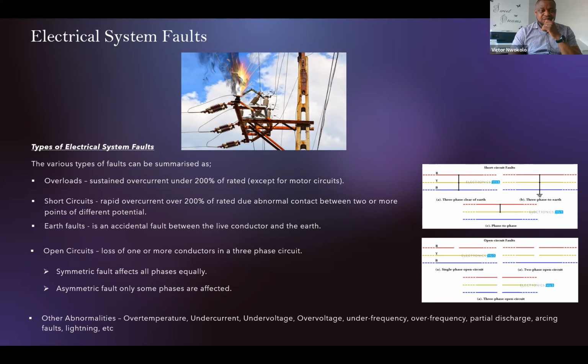We also have short circuit. Short circuit is another very rapid and very common form of overcurrent. It exceeds 200% of the rated, and in many cases, it occurs where two current carrying conductors come in contact with each other. And because they're both at different potentials, you get a reaction between them. And this is due to the electrical phase difference between the two potentials or voltages, if I put it like that. So short circuit is a common type of electrical fault.